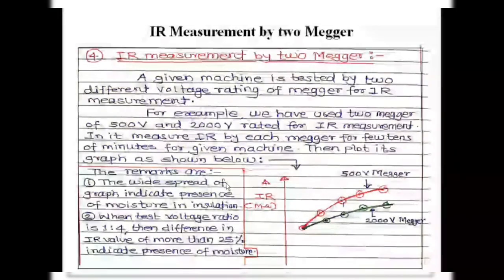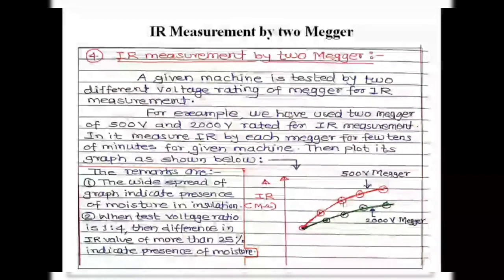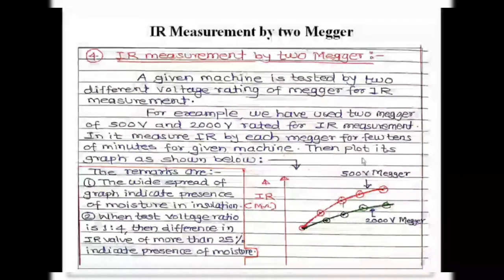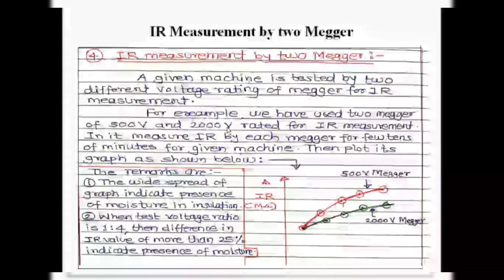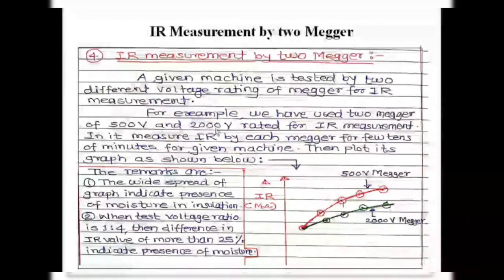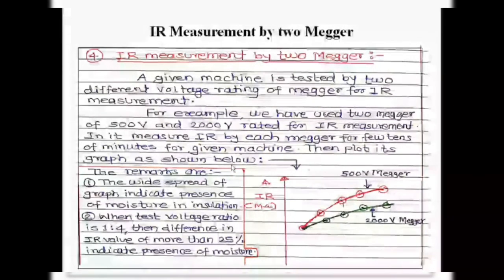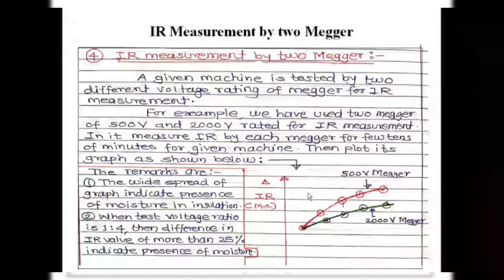The fourth method for interpreting the condition of insulation is IR measurement using two meggers. In all three previous methods, only one megger of a certain voltage rating is used. For this method, two meggers are required — one rated at 500 V and another at 2000 V. Their voltage rating ratio is 1:4. We take insulation resistance measurements using each megger for a few tens of minutes on the given electrical machine, first with the 500 V megger, then with the 2000 V megger, and then plot the graph.